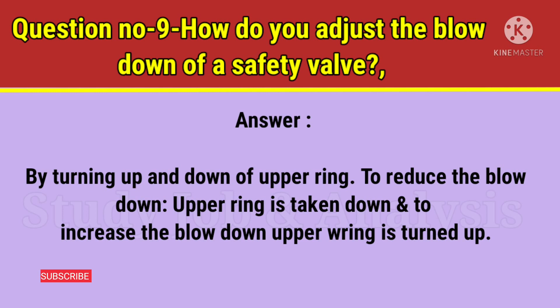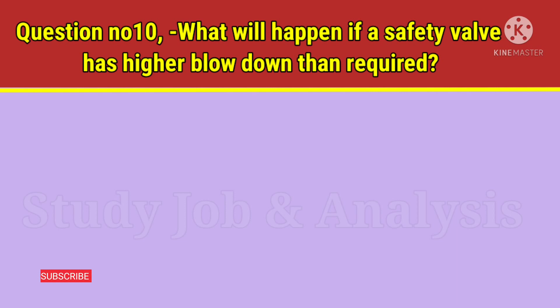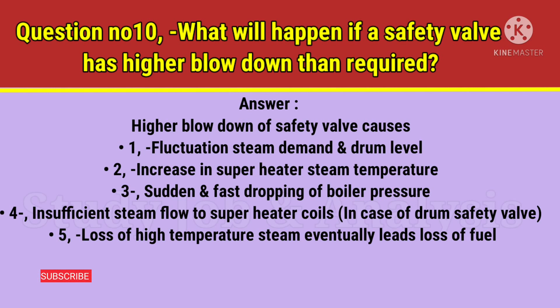Question number 10: What will happen if a safety valve has higher blowdown than required? Answer: Higher blowdown of a safety valve causes: 1. Fluctuation in steam demand and drum level. 2. Increase in superheater steam temperature. 3. Sudden and fast dropping of boiler pressure. 4. Insufficient steam flow to superheater coils in case of drum safety valve. 5. Loss of high temperature steam, which eventually leads to loss of fuel.